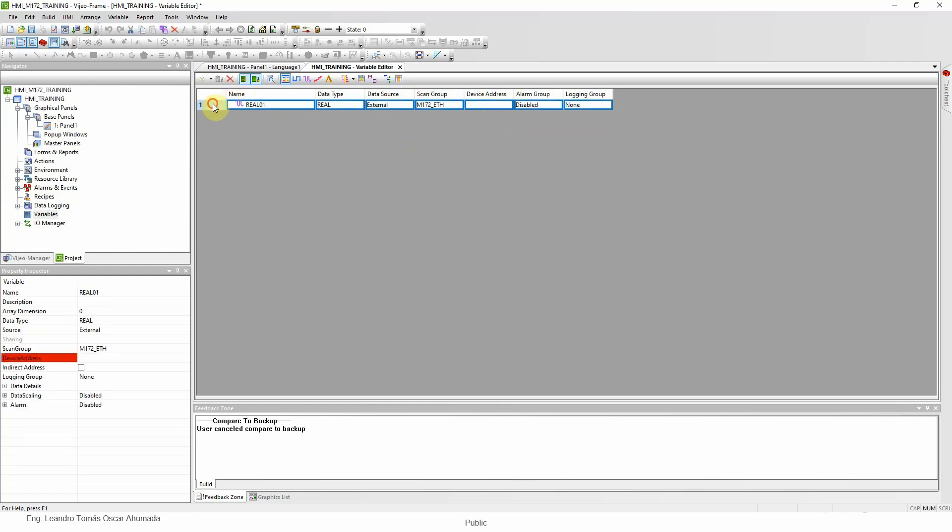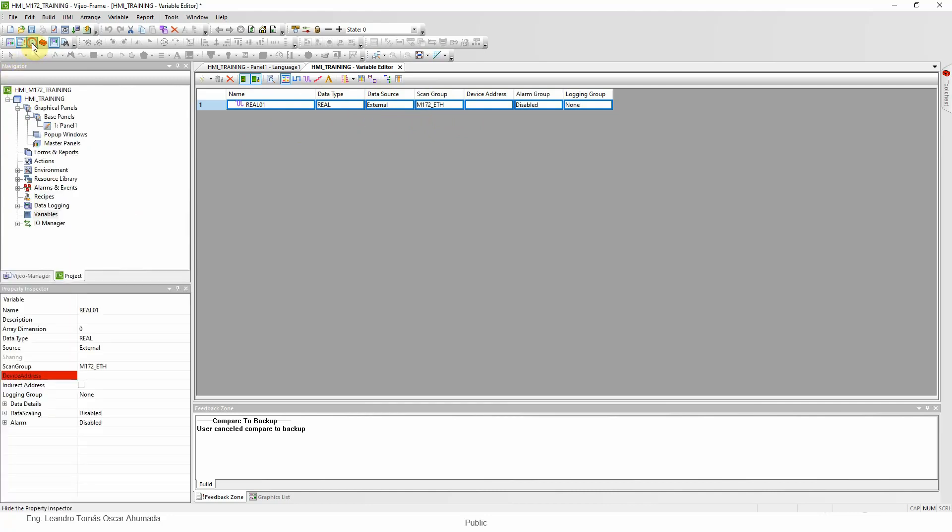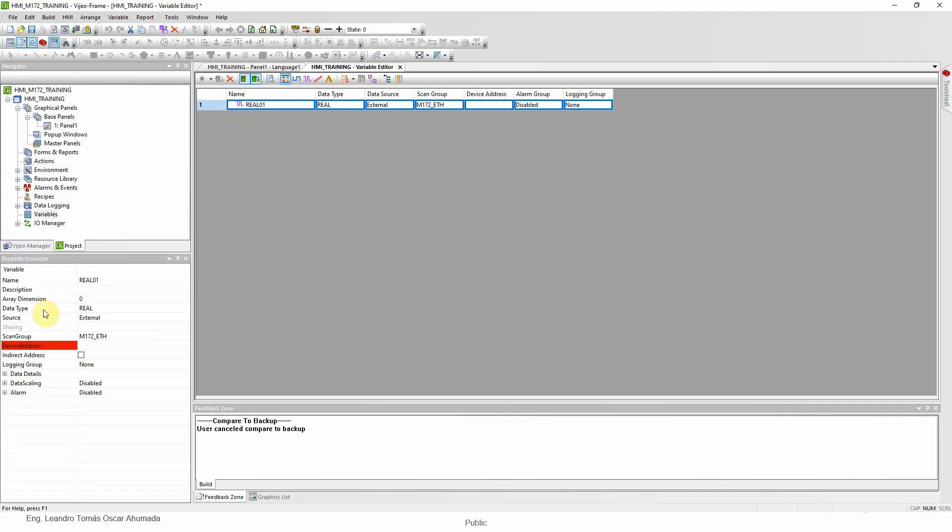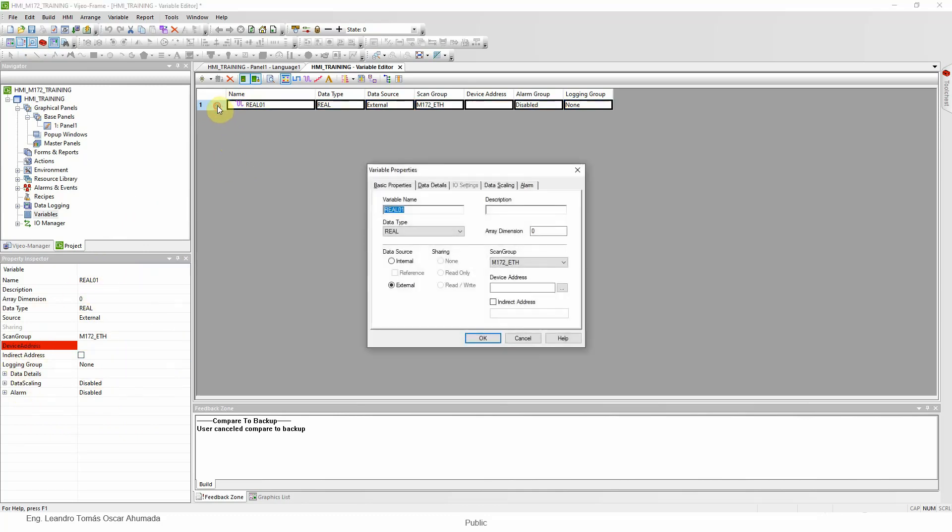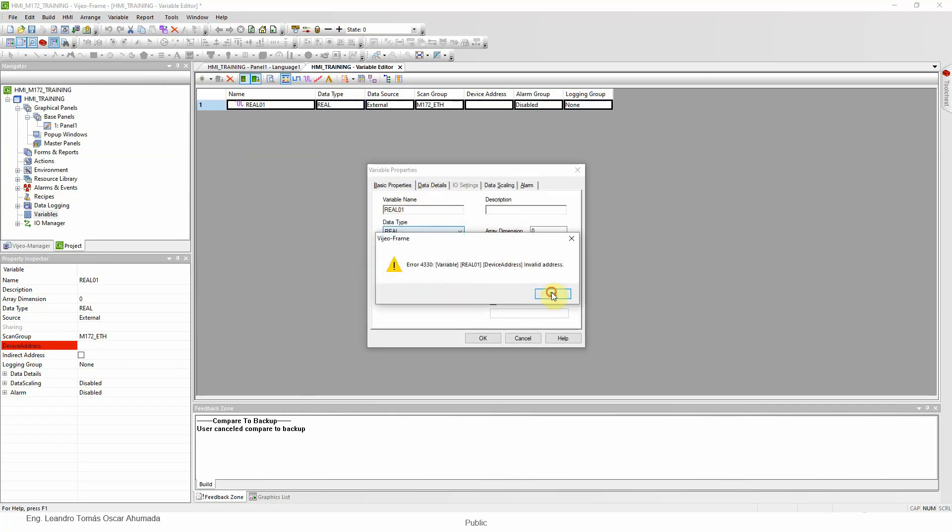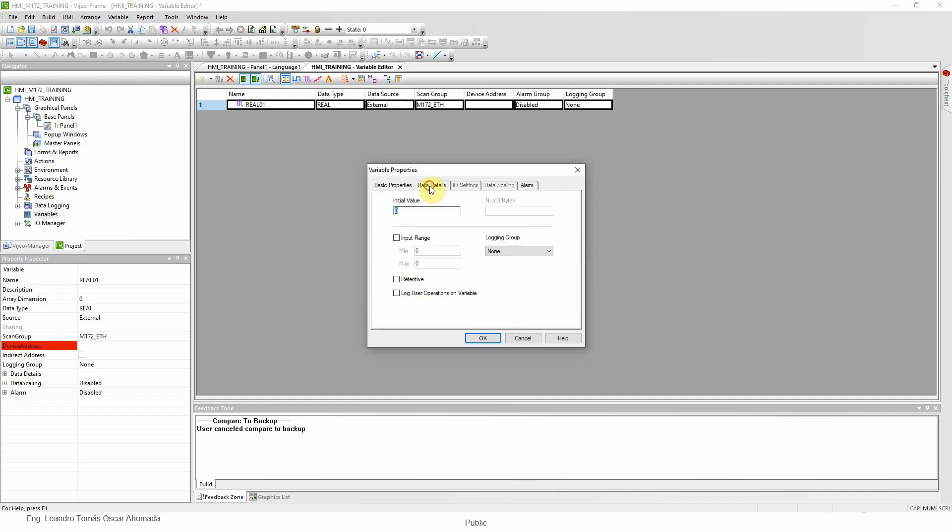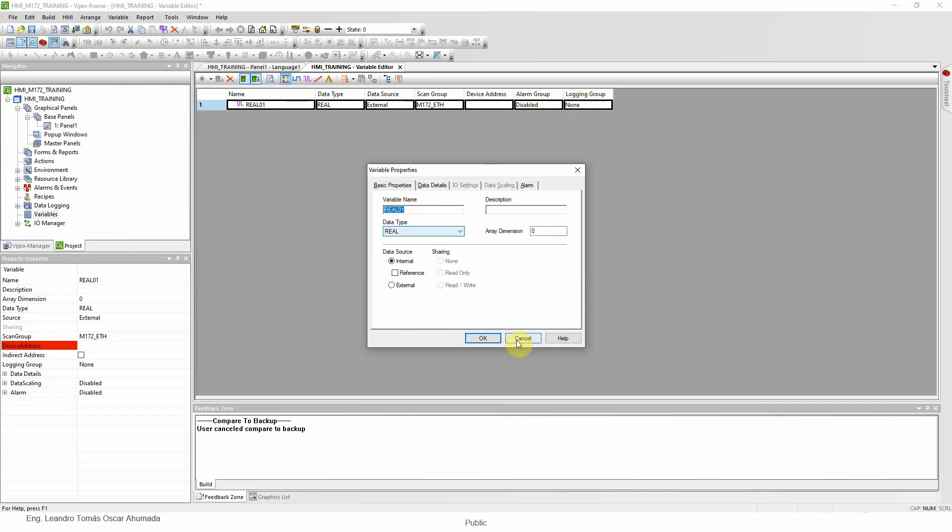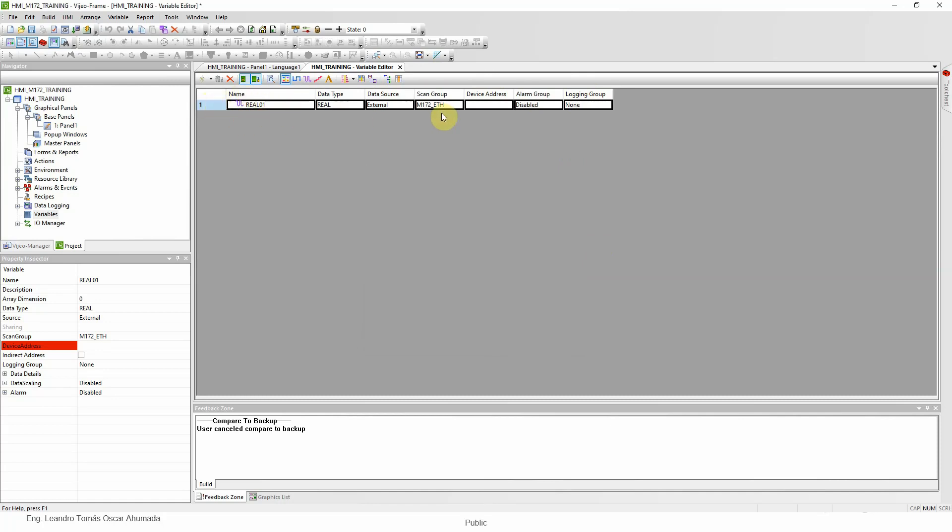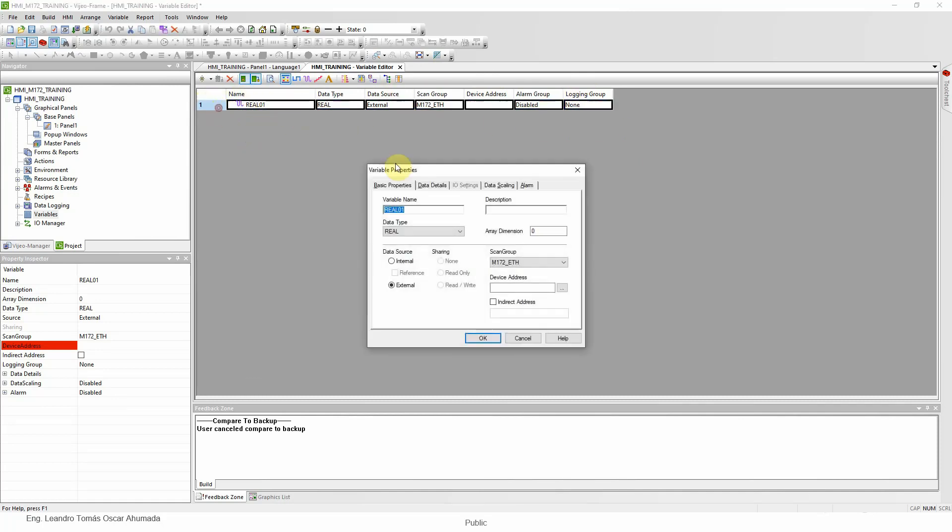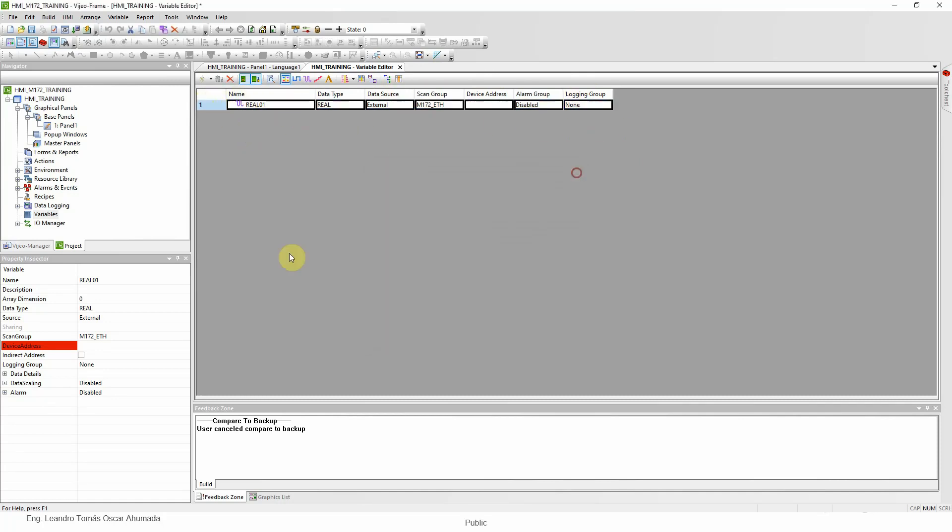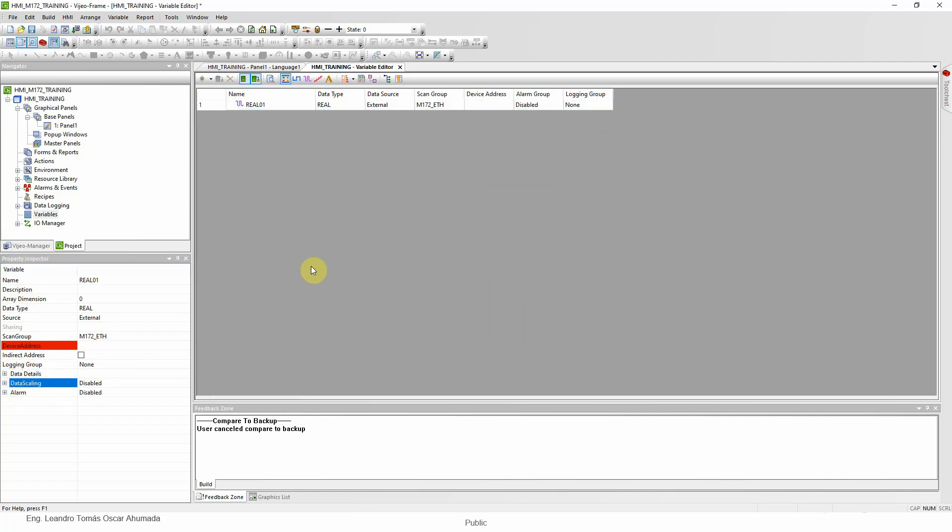There is a faster way to change this information, which is using the property inspector, which is this icon if you are not able to see it. In here you can see more details about the variable. This visualization can be accessed by double-clicking on the variable. You can see internal, external. I need to type an address. Let's put internal. Here we have more details: if it's internal we can put retentive, we have an input range, logging. So for the information about the variable, if we are not able to see it in here, we just double-click and access this information or use the property inspector.